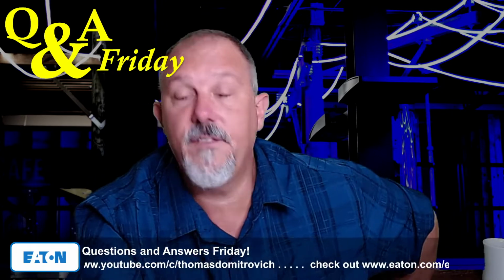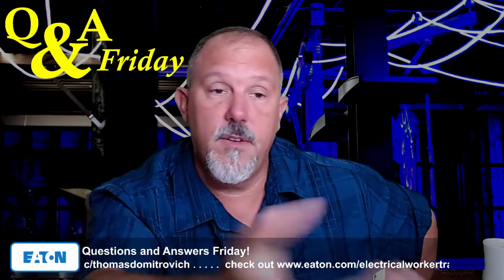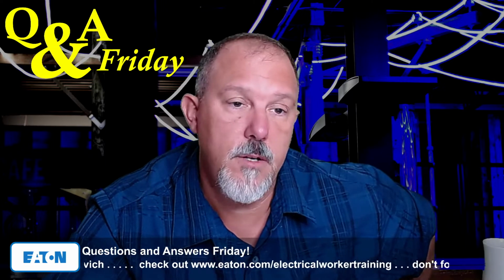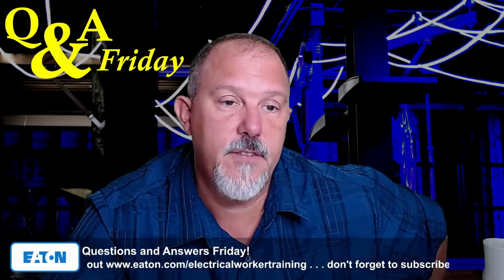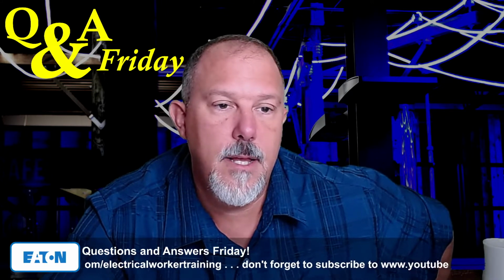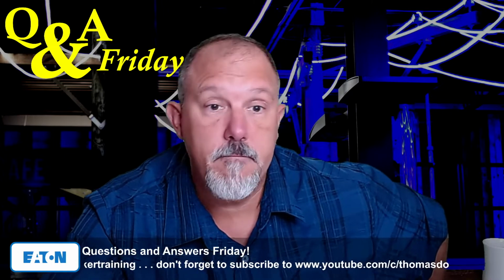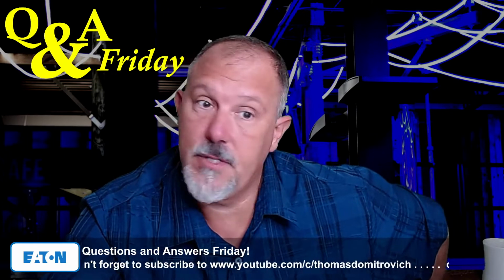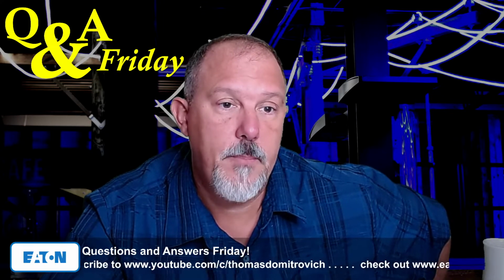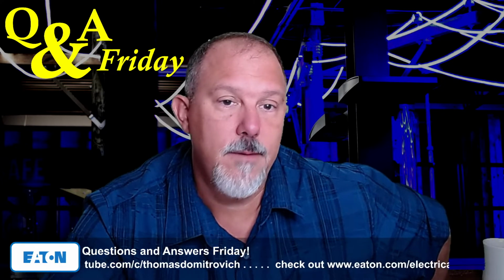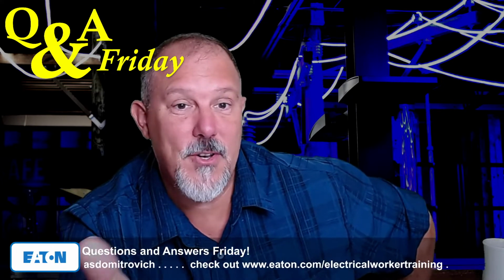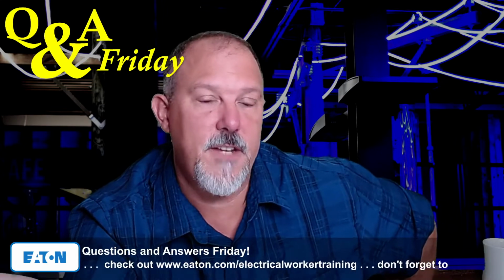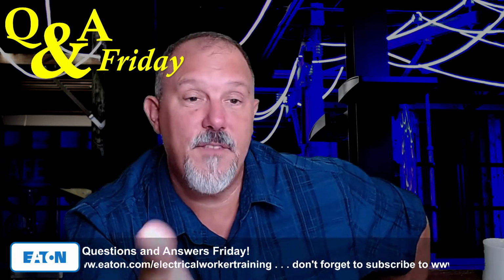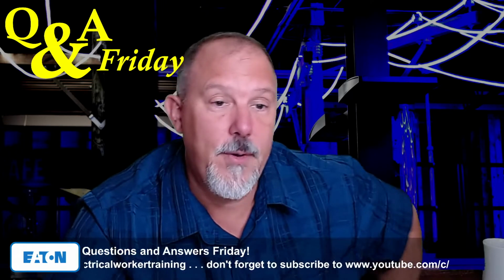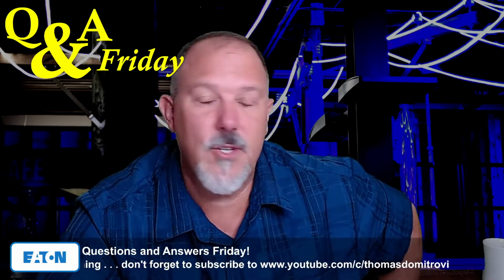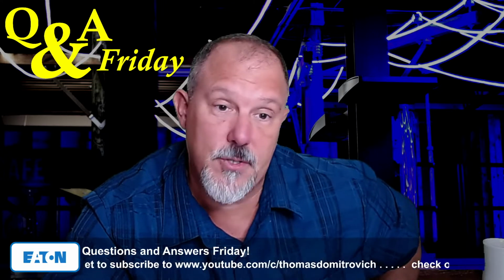And that's my other comment: if I had ground fault protection of equipment, and not even GFCI on there, I would have cleared that long before somebody would have touched it as well. You could very well be right there. Just adding a GFCI device upstream absolutely does not mean that the device will ever be tested, let alone work as needed when it might need to operate. Nothing's guaranteed in life. Absolutely right. But if the wire type equipment grounding conductor was damaged, odds are, but you can't guarantee it either, right? You say odds are, and I could say the same thing, that the odds are the GFCI will do the job. Odds are the GFPE, if you had it on there, would have done the job. Odds are, if you had the equipment grounding conductor there, it may have done the job. So, I mean, odds. If you're a betting man, sure.